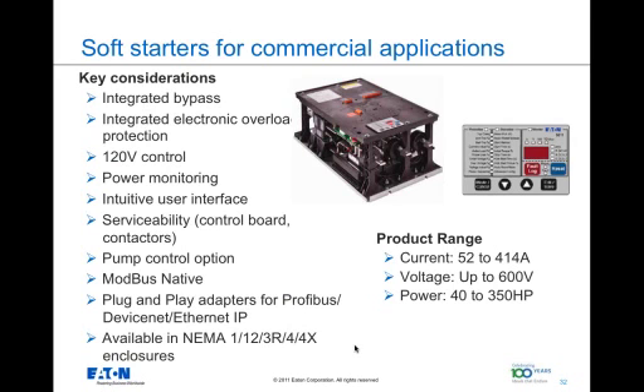If after the soft starter has gone through its useful life of 15 to 20 years, you want to replace the important elements of a soft starter like a control board, that can be done in the field. They need the pump control option for eliminating the water hammer, communication capability on board, and having this particular device in an enclosed control is also a key for this segment of the market.